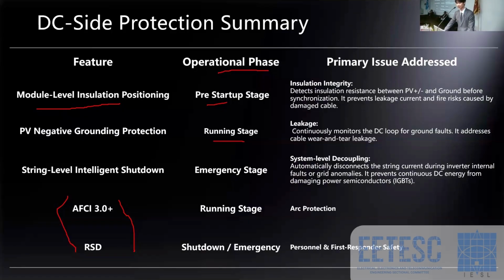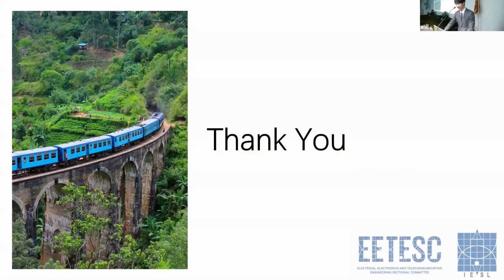At the same time, the app will also give you feedback with a percentage and a code. You can use the percentage to calculate which levels, which PV panels have the highest risk, so you can do the maintenance more efficiently. So that's string level intelligent shutdown. So basically, that's all from my side, as for the DC side rooftop protection method.